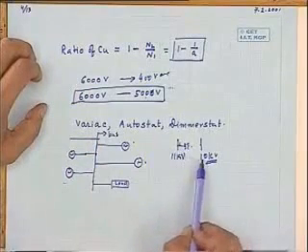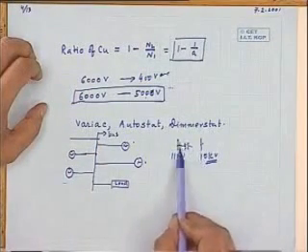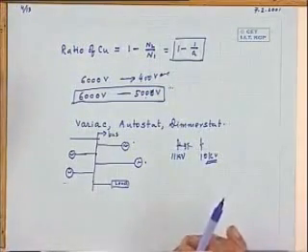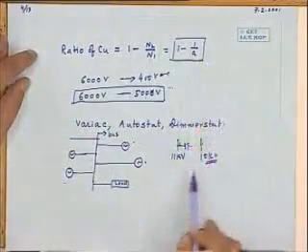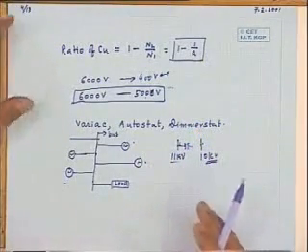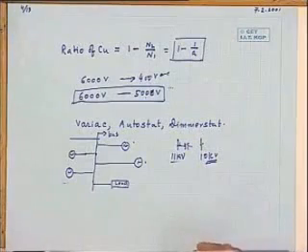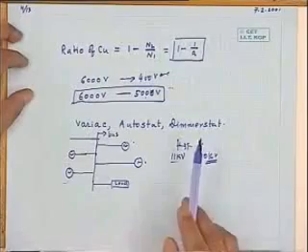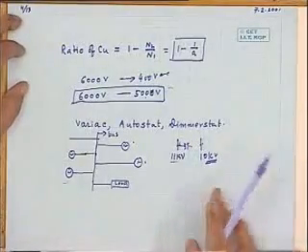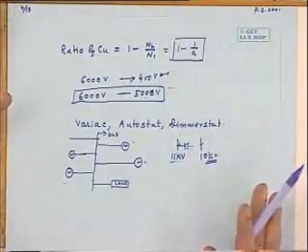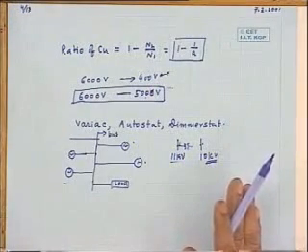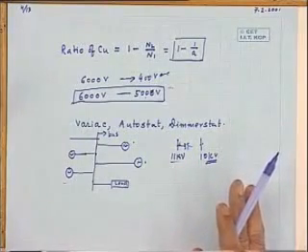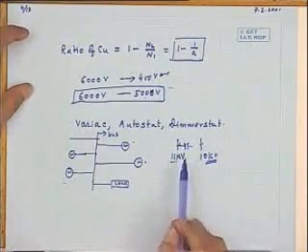You can connect them by a two-winding transformer also, by taking 11 kV to 10 kV and connecting this side there, this side there. They will be parallel. But what I am trying to tell, to take advantage of the auto transformer, here the ratio of the voltage transformation may not be that high, very close to unity. There you connect auto transformers. So auto transformers are widely used to connect two power systems at different voltage levels and the ratio not differing much from unity. That is what I want to point out.